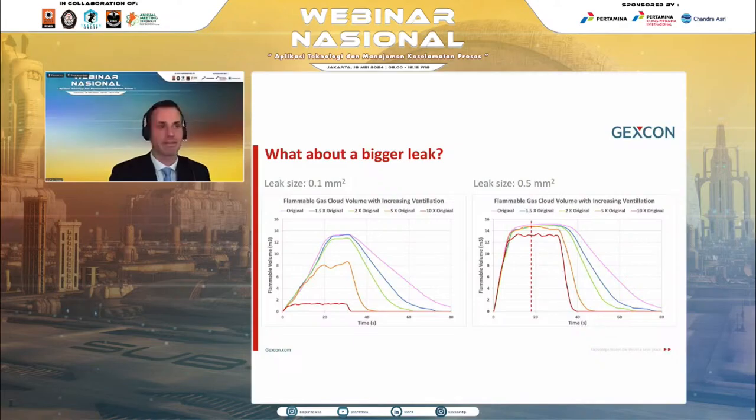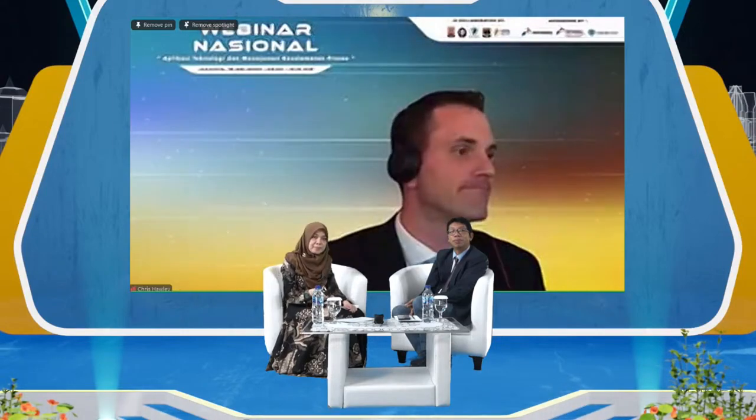Well, basically the conclusion from the case study was that CFD modeling was able to provide a much more accurate understanding of the system behavior to help inform design decisions. It provided a dynamic model against time to give an understanding of the sensitivities of the system for different ventilation rates, to help with the cost-benefit analysis and also potential justifications. And it revealed consequences from the system that weren't anticipated by the design team, which I had on my previous slides. But that's it.